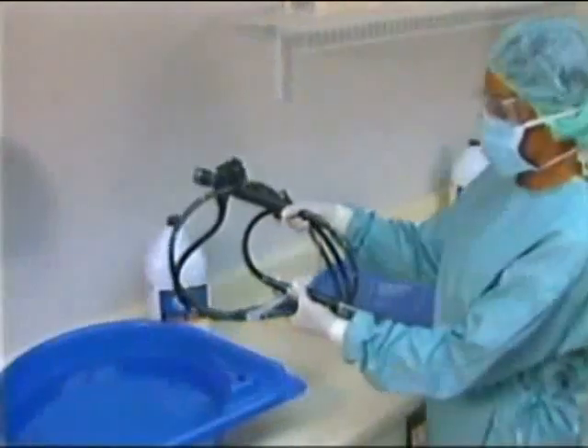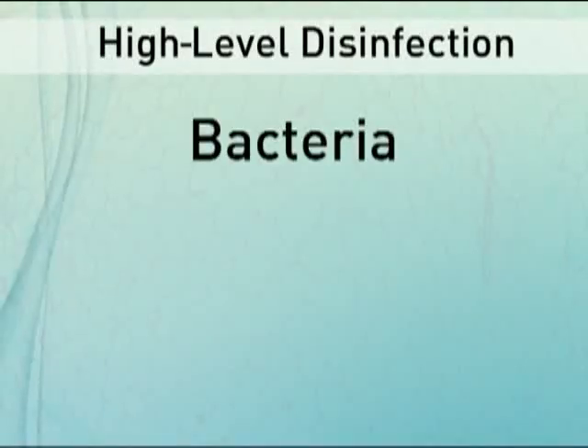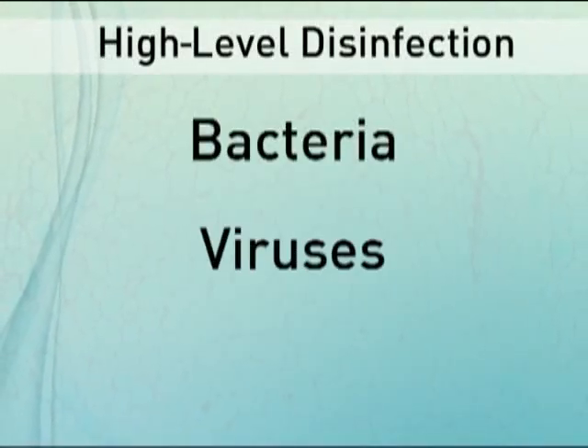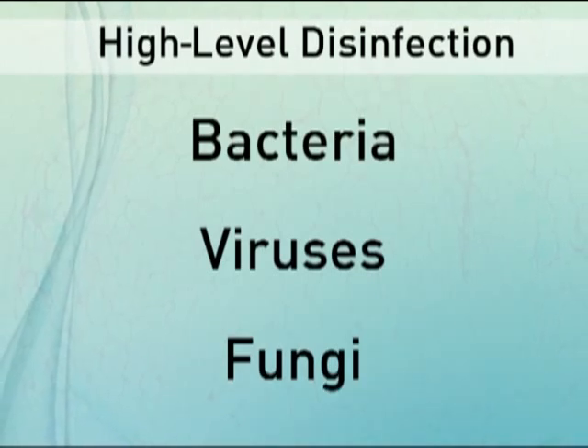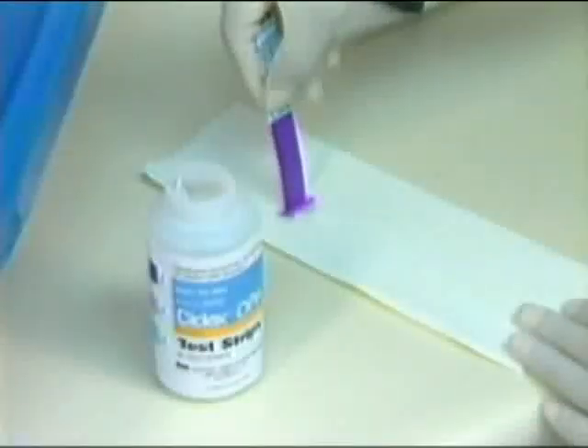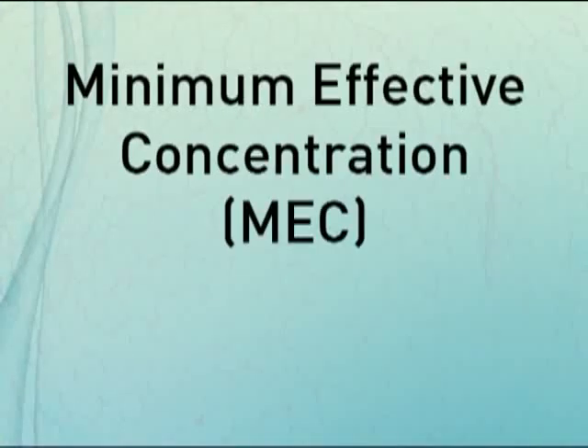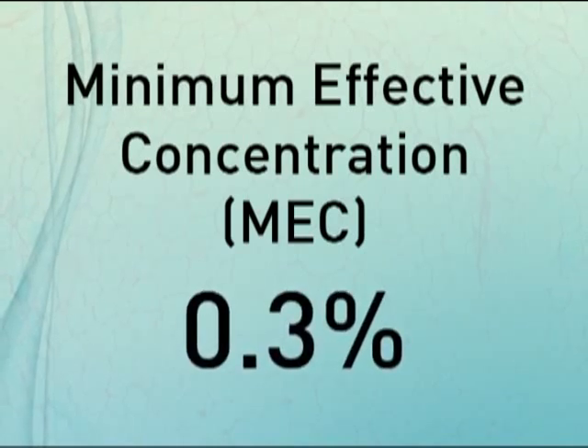High-level disinfection destroys microbial activity of bacteria including TB, viruses such as HIV, and all fungi. The MEC of the solution may be verified by Cidex OPA solution test strips. The minimum effective concentration is 0.3%.